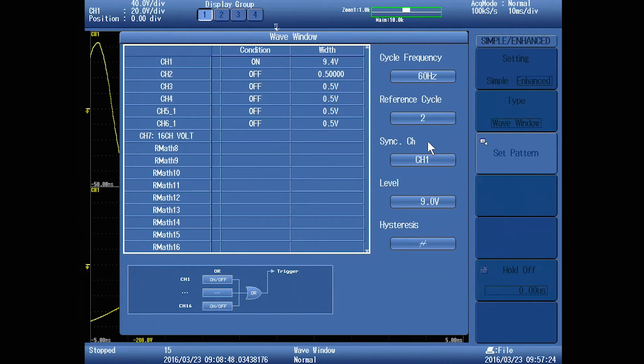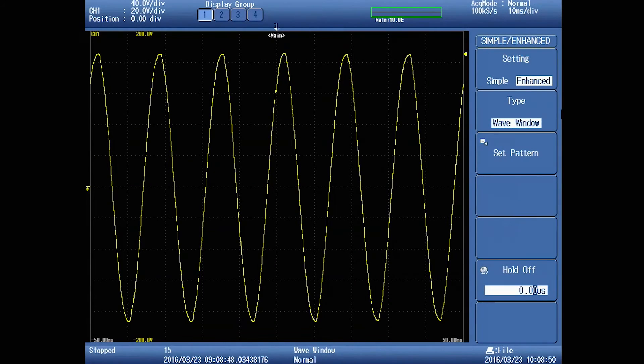Let's talk about what to expect during this test and discuss how this trigger works. When I force the UPS to switch over to its internal inverter and batteries, a very small glitch, seen here, occurs in the otherwise very smooth filtered output of the UPS.